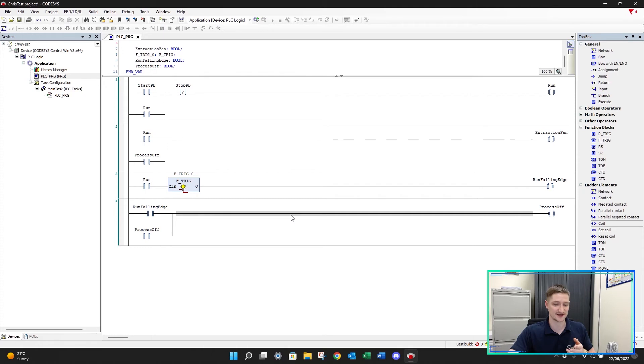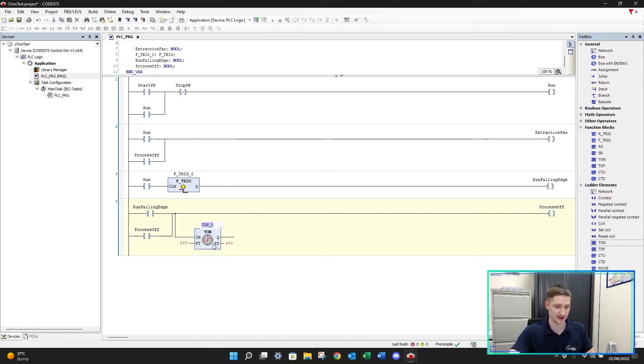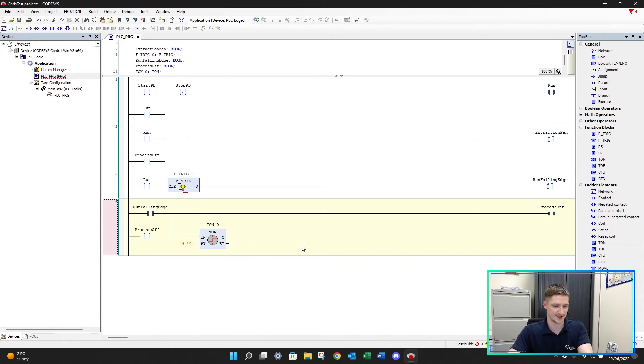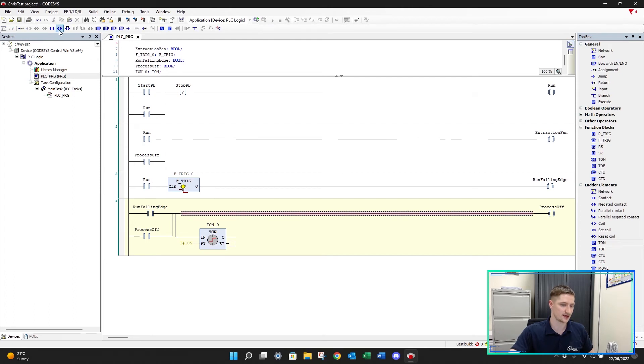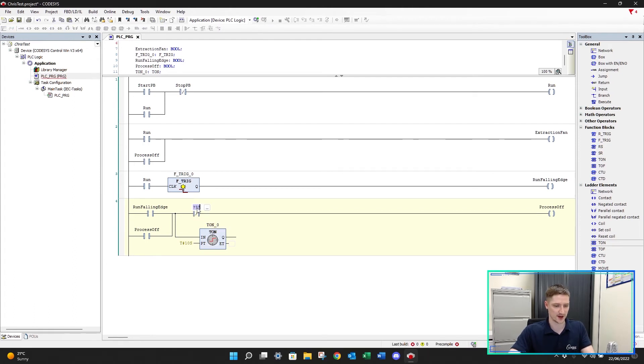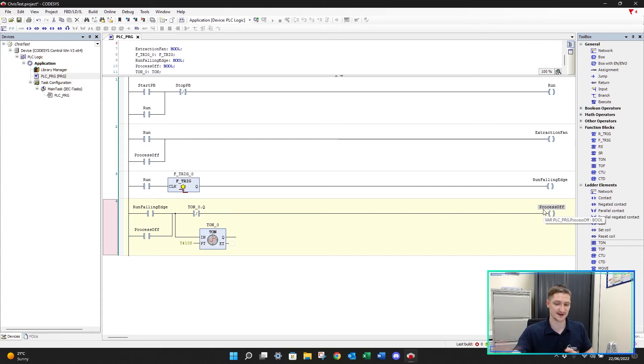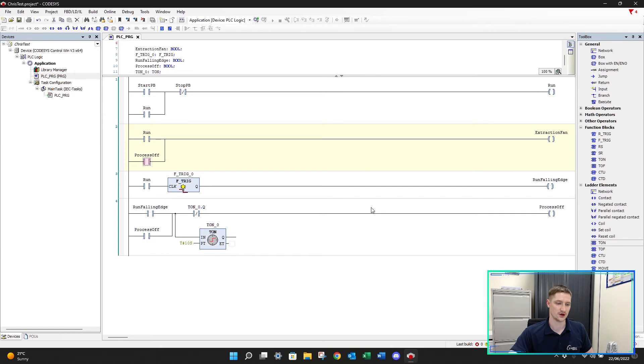I then want to run a delay for 10 seconds. If I branch down from here and put in a standard on delay timer - TON zero - I'll take that to T# 10s. When this timer has finished, I want to turn off the 'process off' signal. Using a normally closed contact on TON.Q, that will pulse for 10 seconds and then reset 'process off', turning off this whole process. That now reacts just like our off delay timer.